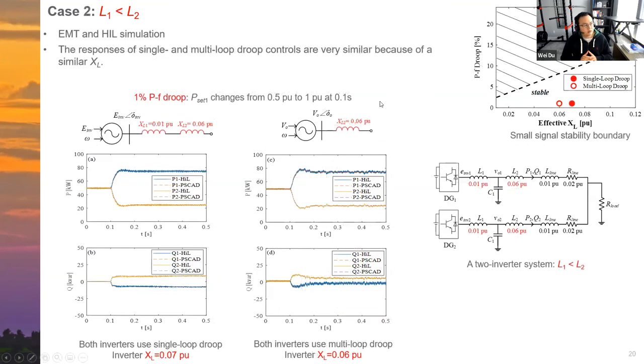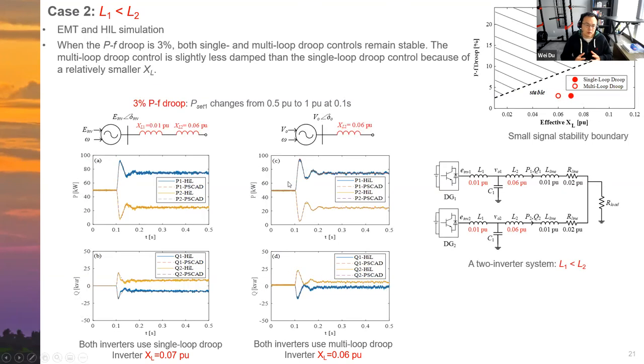And then let's take a second case, case two. For this case, we exchange the values of L1 and L2. We make L1 much smaller, just 1%, and L2 now is 6%. So based on that circuit at the fundamental frequency, we can see that both the CERTS droop control and the multi-loop droop control have very similar coupling reactance, right? Because the CERTS droop control has 7% coupling reactance, and the multi-loop droop control has 6%. Then we should expect a very similar dynamic response. Looking at the simulation, if both controls have 1% droop gain, their dynamic responses are very similar.